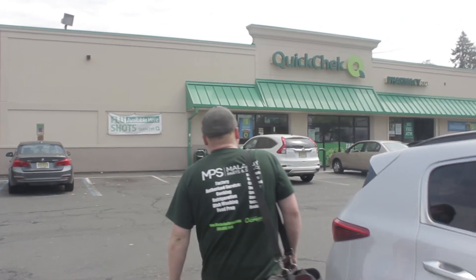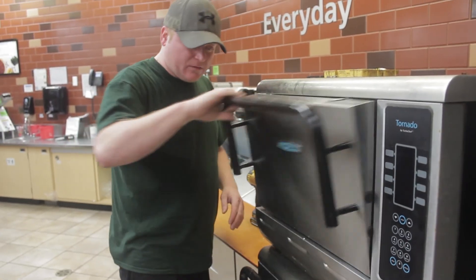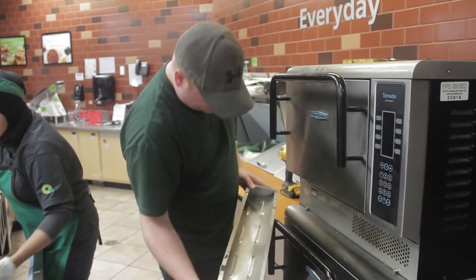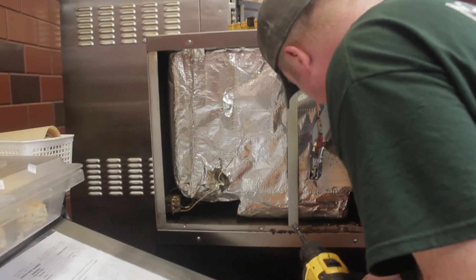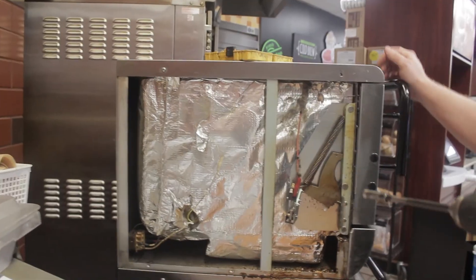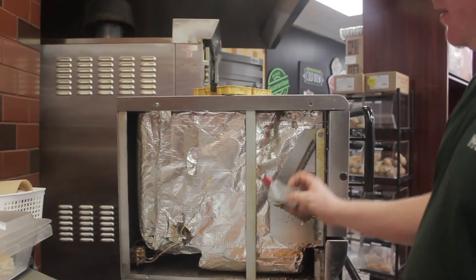We're here at QuickChek, working on one of the Turbo Chefs. Basically they called up saying that the oven door was closed but it wasn't registered, and it would say oven door is open. Opened it up, found that the left side primary switch kit was hanging — the screws that mount to the actual unit were missing.